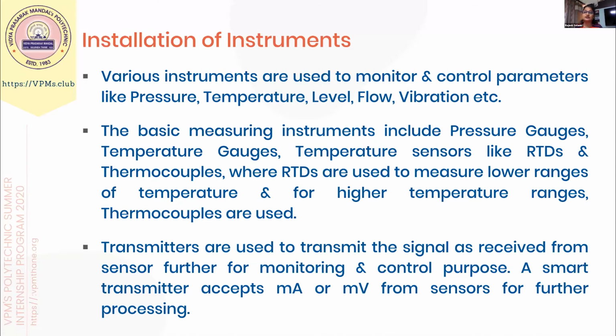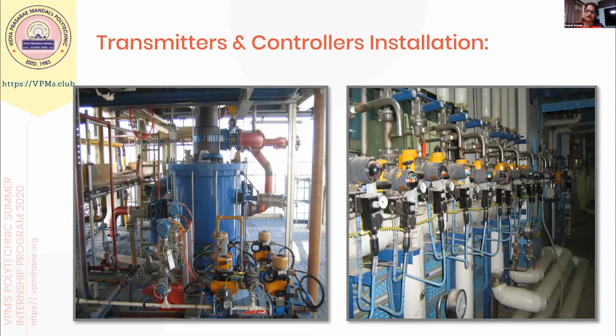Then transmitters. Transmitters are used to transmit the signal received from the sensor further for monitoring and control purposes. Like if the temperature in a vessel is to be displayed somewhere, the sensor will sense the temperature of the vessel and transmit that signal to an indicator installed anywhere in the plant, or in a control room too. A smart transmitter accepts a milliamp or millivolt signal from the sensors for further processing. So these are the transmitters and controller. You can see the installation in the plant.